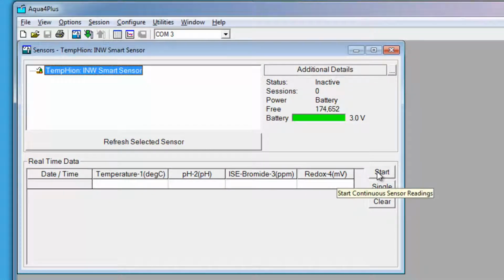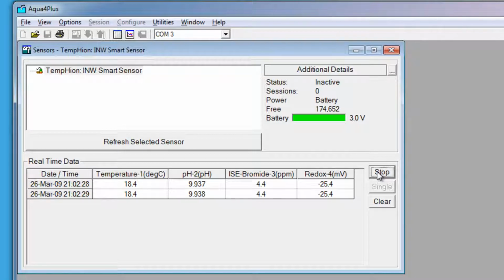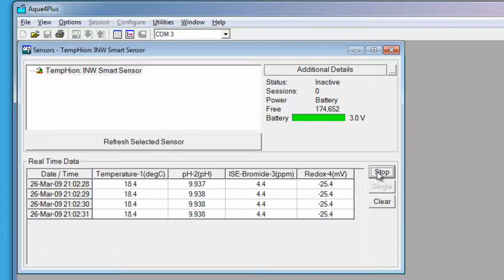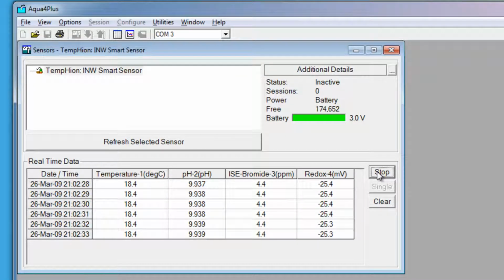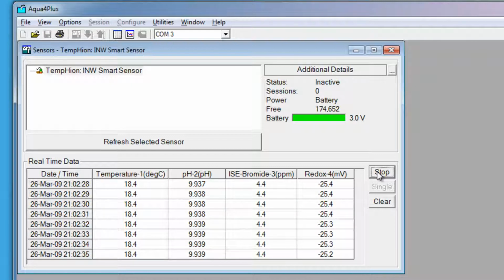And then we can verify the calibration by taking real-time readings. And again, you want to check for stability. And everything looks good. And that is how you perform a 2-point calibration on pH on the AquiStar Temphion.